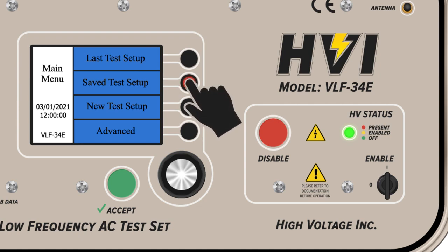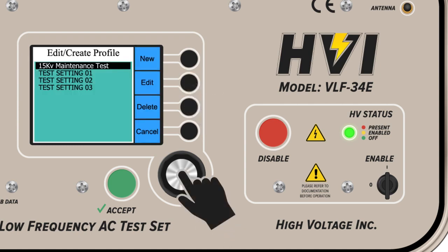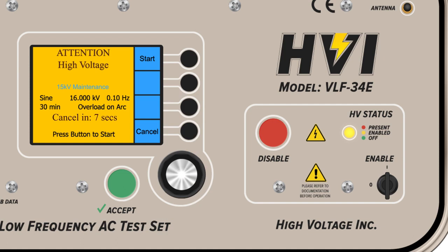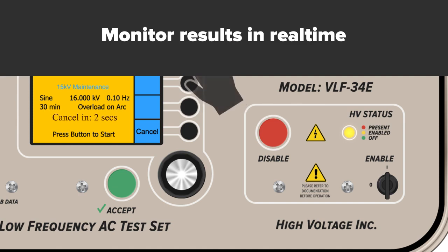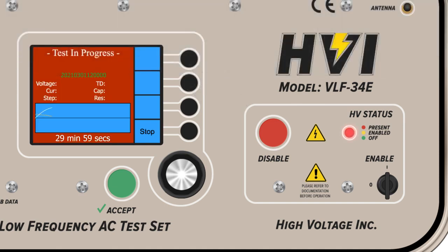Once the profile is selected, the screen will turn yellow and a 10-second safety countdown will begin. If all safety parameters have been met, begin the high voltage test by pressing Start again. Monitor the results in real time via the display screen. Data will populate after the first full wave cycle has been completed. Abort at any time with Disable button or safety provisions.